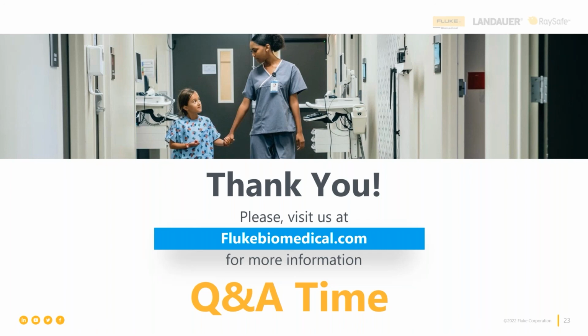Okay, great. As it relates to 61010, does it have to be done in every electrical safety testing schedule? Absolutely not. It is done, as I said, by the manufacturer in their final assembly test and design validation testing. And it is done by the installer when the clinical laboratory equipment is installed in the hospital clinical lab or in the freestanding clinical laboratory. And then from that point forward, we use IEC 62353 for routine testing.